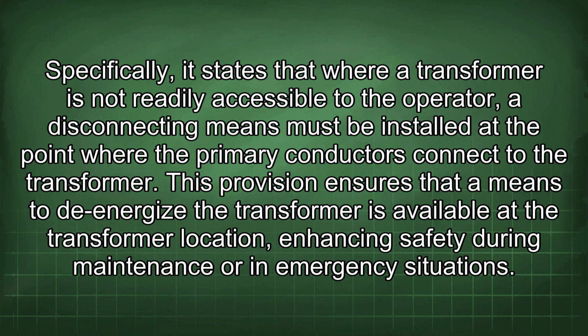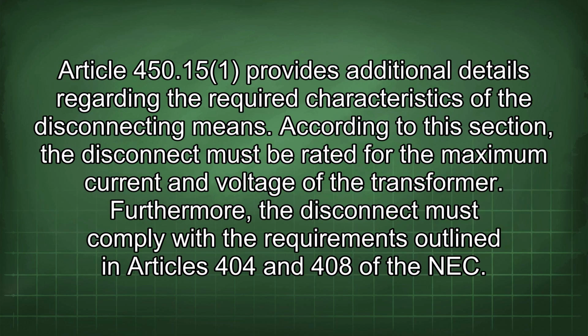This provision ensures that a means to de-energize the transformer is available at the transformer location, enhancing safety during maintenance or in emergency situations. Article 450.15(1) provides additional details regarding the required characteristics of the disconnecting means. According to this section, the disconnect must be rated for the maximum current and voltage of the transformer. Furthermore, the disconnect must comply with the requirements outlined in Articles 404 and 408 of the NEC.